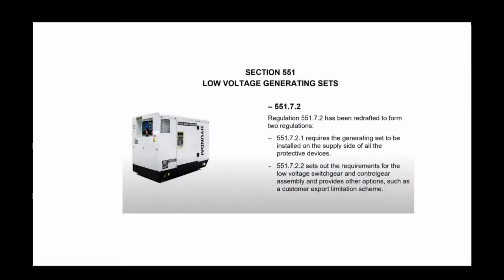The next part in 551.7.1 is just to clarify what we've already spoken about in Amendment 3, so using bidirectional protective devices, although the wording is likely to change because since we put it in here, we've obviously gone through the DPC process and we've gone away from the term taking account of the direction of power flow. So that'll likely, well, it will align with what we've got in Amendment 3. Yep. And then we move on to 551.7.2, and that's now been split into two parts.